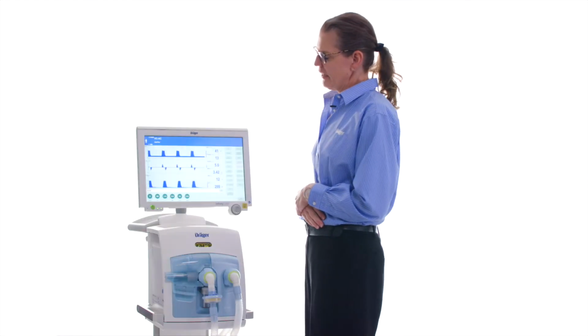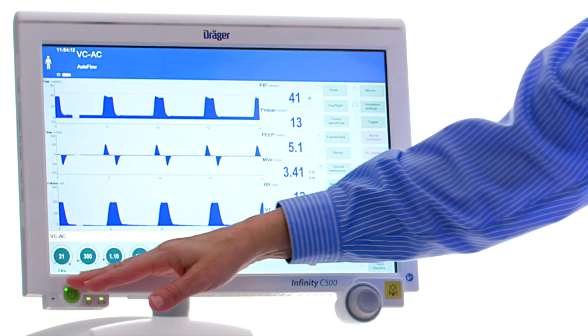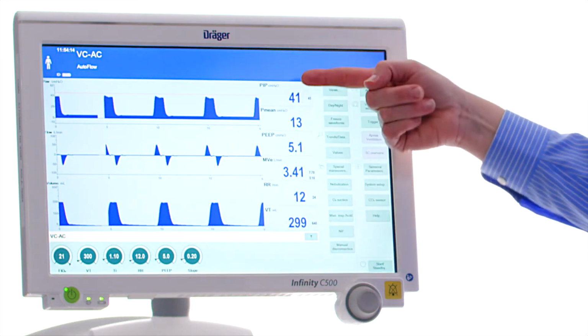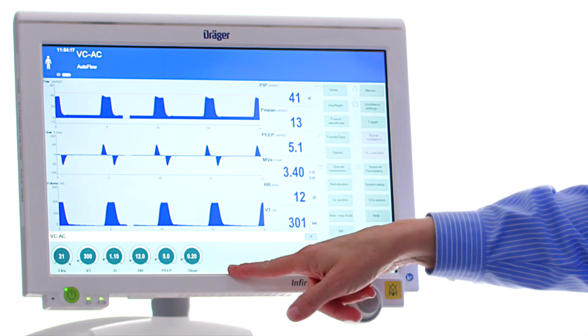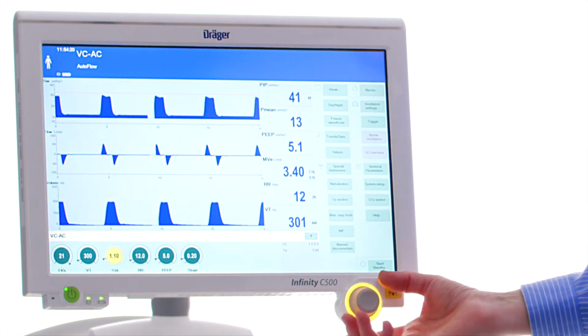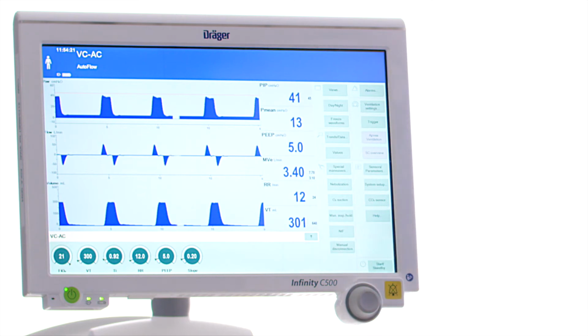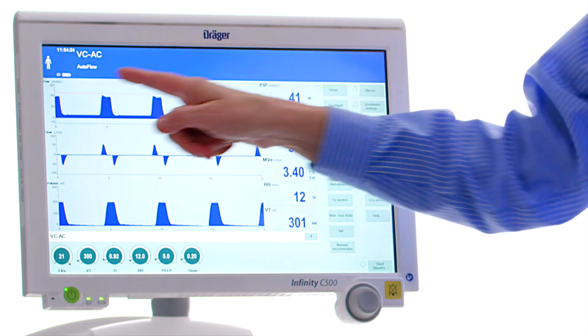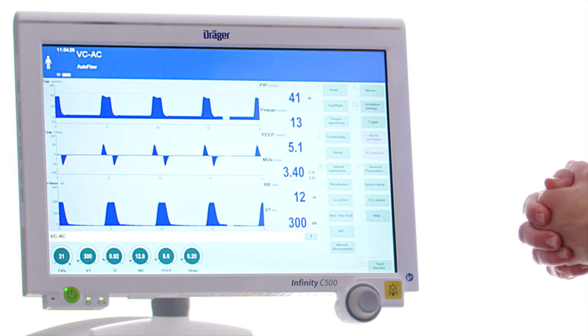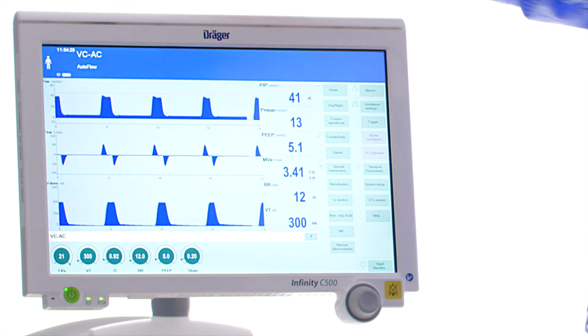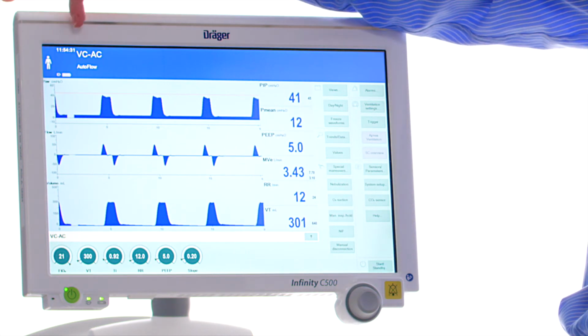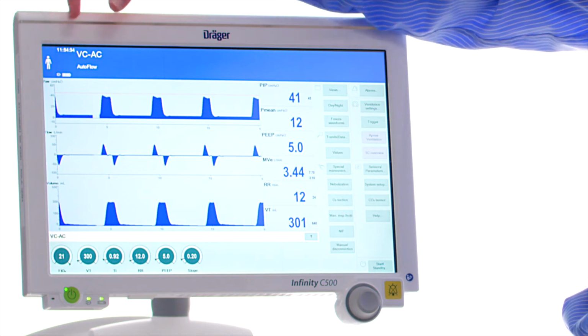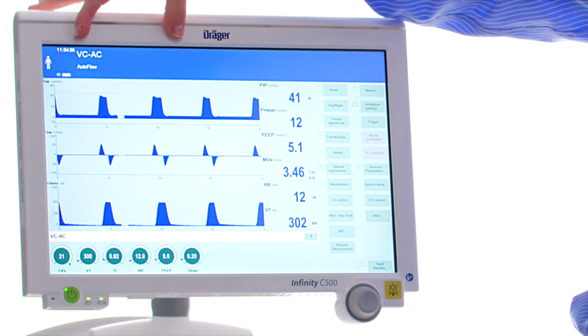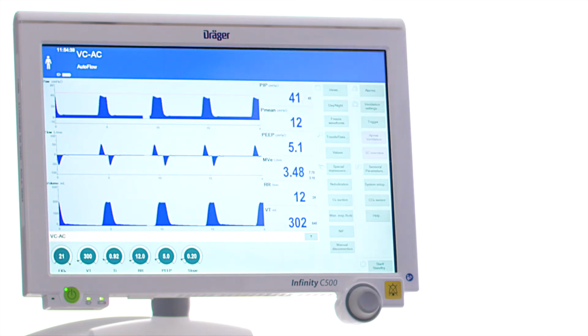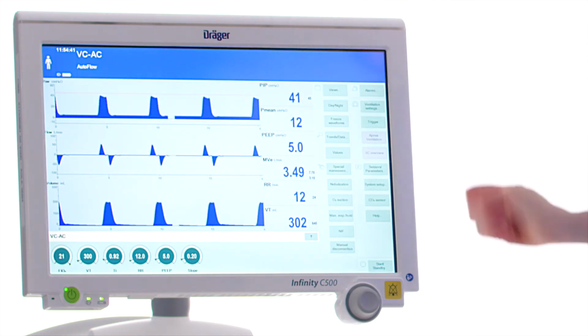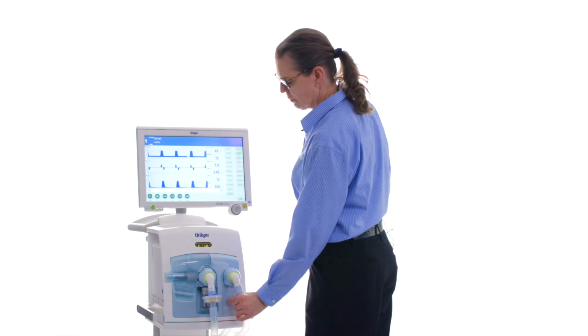Once we begin ventilating, the basic layout of the screen: your ventilation parameters sit across the bottom. Anything blue is measured, green is set. To make changes, touch the button, turn the knob, confirm. Touch, turn, confirm is the magic. In the center of the screen, you're going to have your graphics, and then across the top of the header bar, we're going to find our patient category, clock, and battery life indicator, and then the mode of ventilation and any additional adjuncts. Across the right-hand side of the header bar is where ventilator alarms will be displayed.